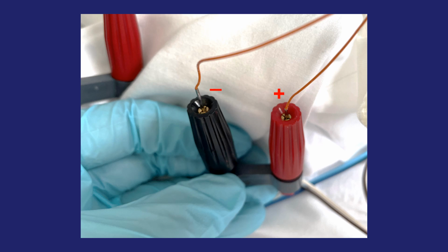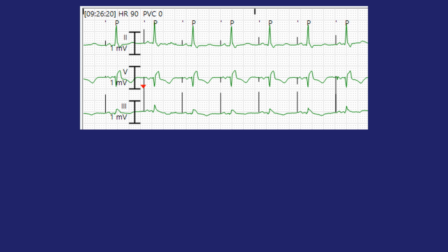Here's a close-up view of one of the ventricular wires attached to the cathode port here. When this screw is loosened, righty-tighty, lefty-loosey, this little opening becomes a little wider and this pin can be slipped in, making metal contact to the metal graspers, and then this is tightened around so the pin can't slide out, making sure metal is contacting metal, and the same thing for the anode. So this external pacer box will function just like a standard permanent pacemaker that has two leads, if in fact there are two sets of epicardial wires.